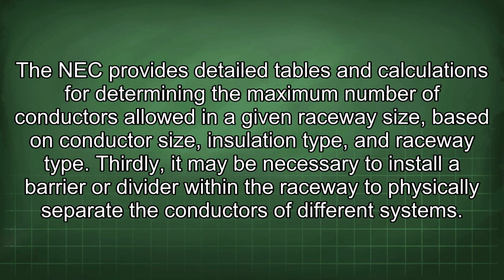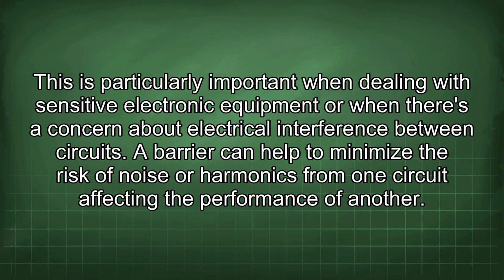Thirdly, it may be necessary to install a barrier or divider within the raceway to physically separate the conductors of different systems. This is particularly important when dealing with sensitive electronic equipment or when there's a concern about electrical interference between circuits.